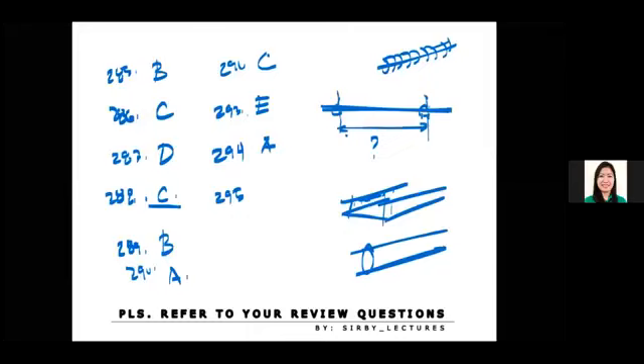For rigid metal, the maximum spacing is 3 meters. But for rigid non-metallic conduit, we have a maximum spacing of 0.9 meters. And of course, you can think about it that if you have a rigid metal, then the flexural resistance is greater as compared to non-metallic conduits. So the answer for 295 is letter C. For 296, this is letter B. And for 297, the answer is all of the above, letter D.